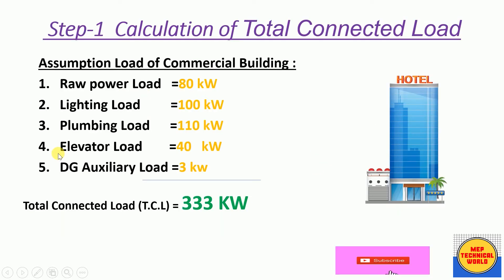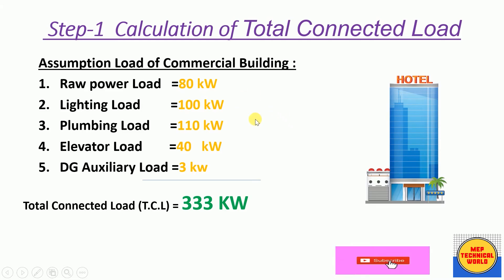In Step 1 we have to calculate the total connected load. Suppose we are calculating the total connected load of a hotel building — a commercial building. In this building: total raw power load is 80 kW, total lighting load is 100 kW (including ceiling lights, facade lights, landscape lights, and others), plumbing loads are 110 kW (including filter pumps, hydro-pneumatic pumps, etc.), elevator load is 40 kW, and DG auxiliary load is 3 kW. The total connected load (TCL) = 80 + 100 + 110 + 40 + 3 = 333 kW.